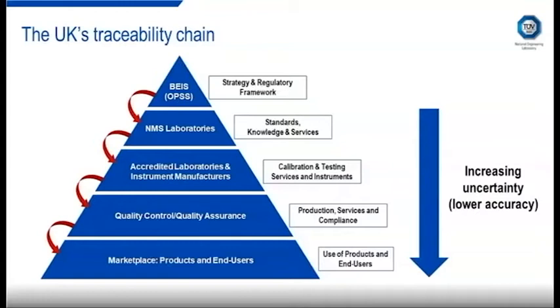The next level down is the NMS laboratories, such as NEL, and this is where the physical and documentary standards for various different measurement types are developed, and these serve as a reference point for the measurements taken in the wider economy. So the next level down from that would be accredited laboratories, which are not part of the national measurement system, but are traceable to those laboratories. And we continue to move away from the top of the pyramid. And as we're doing this, we're increasing the overall level of measurement uncertainty and decreasing the overall level of accuracy. But we still maintain this traceability as we do this.